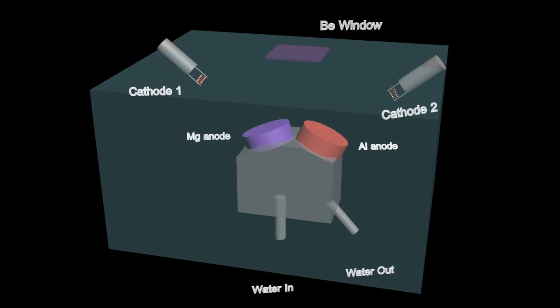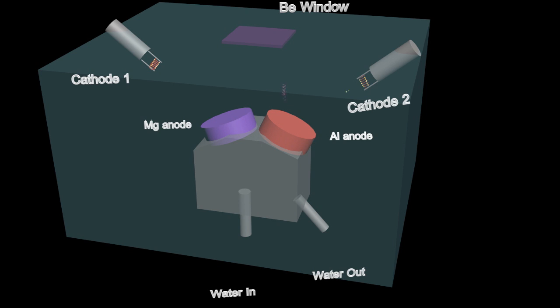There are also other types of x-ray sources such as the twin anode x-ray tube and the rotating anode x-ray tube. In the case of twin anode systems, the anodes are made from different materials and only one of the anodes is bombarded with the electrons at the same time. This allows fast and easy switching between the two exciting energies, and if one of the anodes should fail, then the other will serve as a backup.